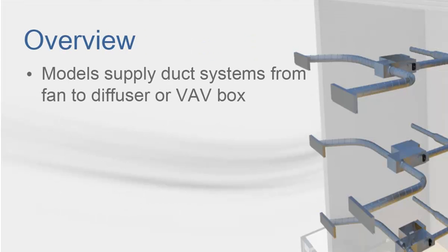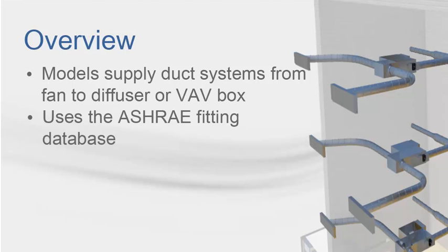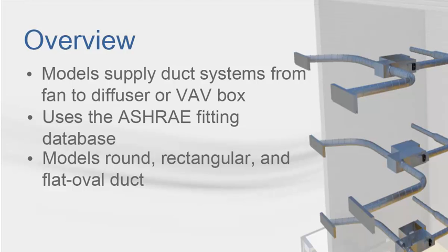Duct Designer will model supply duct systems from the main fan all the way to the diffuser or VAV box. It's important to note that this software is used to design supply ducts, not return ducts. The ASHRAE fitting database is included with the application. It's possible to model rectangular, oval, or round ductwork in Duct Designer. Transitions and junctions are available in the program that allow you to move between form factors as you create your design.